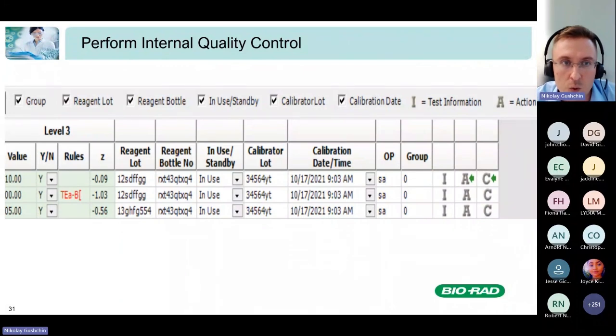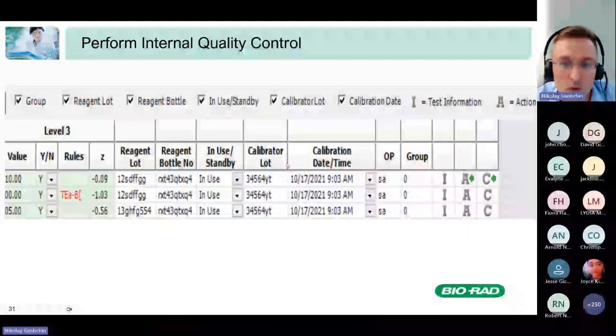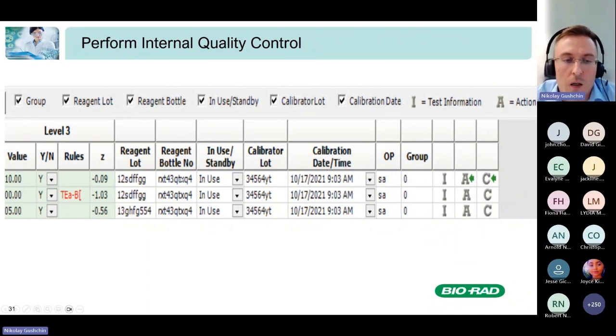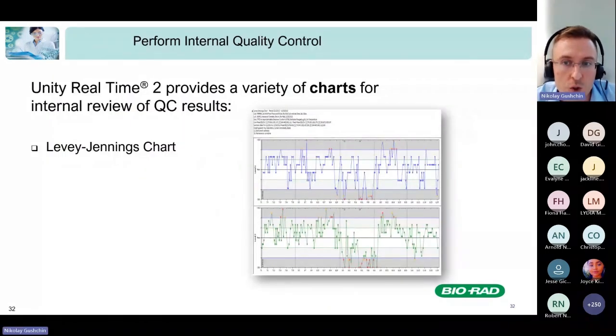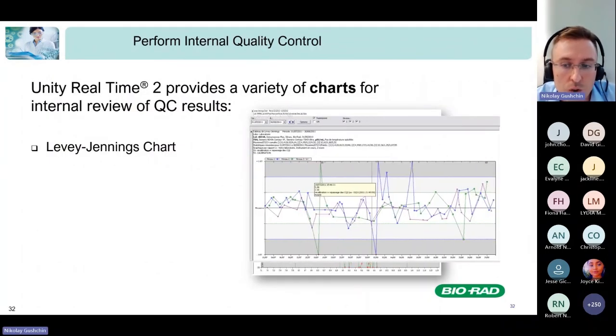Another thing available in Unity is that you can also track reagent lot information, reagent bottle information, even if it is in use or standby for the new and big instruments. You can also track calibrator lot, and you can also type into the program the calibration date and time. So it gives you additional information about your system, and it will help you to troubleshoot. And of course, we have a variety of charts, Levey-Jennings charts, multi-Levey-Jennings charts, where we can combine the data from different levels or different analytes and see the picture.